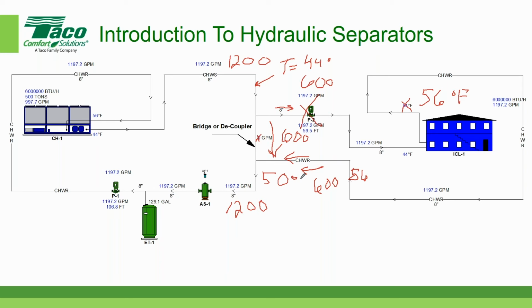50 degrees Fahrenheit. So that means the chiller originally started off getting a return water temperature of 56 degrees Fahrenheit. Its return water temperature now is 50 degrees Fahrenheit. So that makes the chiller not as efficient as we'd like it to be. The building still gets the 44-degree water, but the return water temperature, the mixed temperature at this point, is now going to be lower. Does anybody have any questions about that? Kind of an important concept.